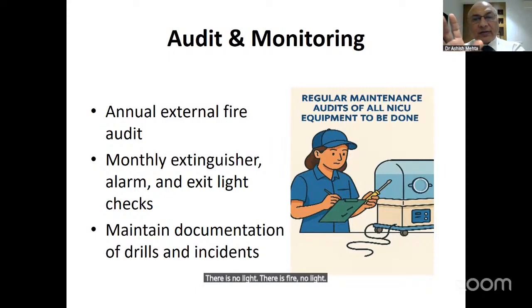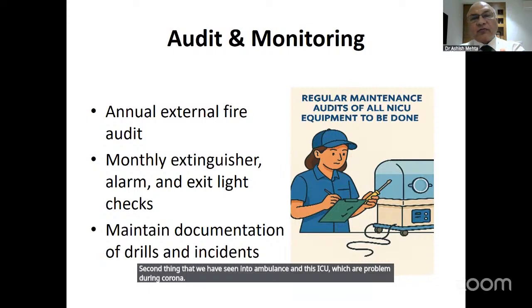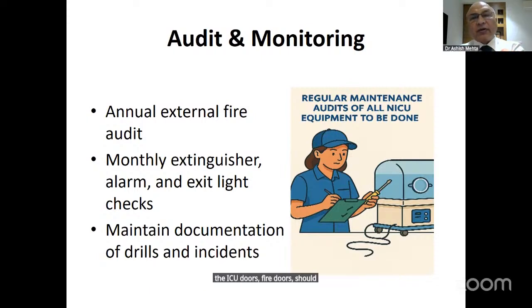Second, we've seen this problem in ambulances and in ICUs during Corona - fire doors should not have a locking system. Normally, even for routine use, our ICU door entrance is opened either with a switch or an iCard that you swipe. The moment the light goes out, these doors auto-lock, and you can't get out. There is a fire, and you can't get out of the ICU. The same thing happens in ambulances.